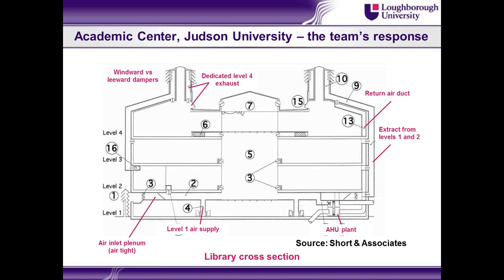So when we move into those extreme temperatures, middle of the summer, middle of the winter, then we'll close down these ventilation stacks on the top of the building, and we will duct stale air through the return duct on the outside of the building here, and bring it down into an AHU at the bottom, where some of it will be expelled, and some of it will be recirculated. So we've got a full mechanical ventilation and cooling system running in parallel, at the time of the year when the passive system doesn't work.